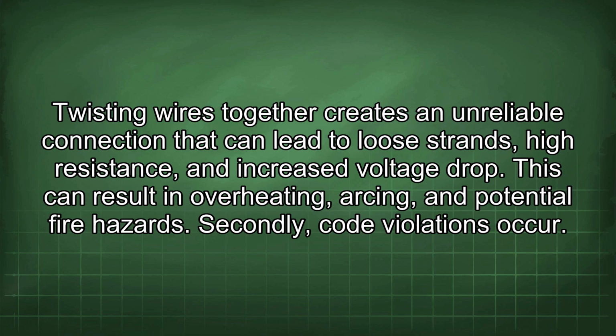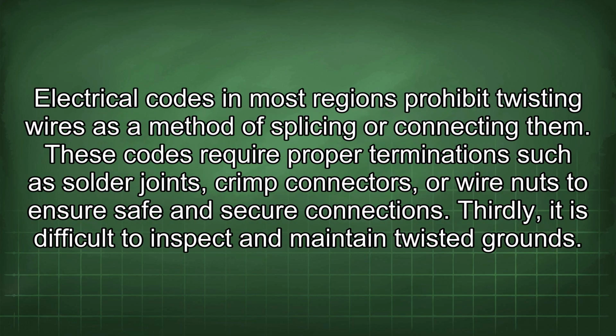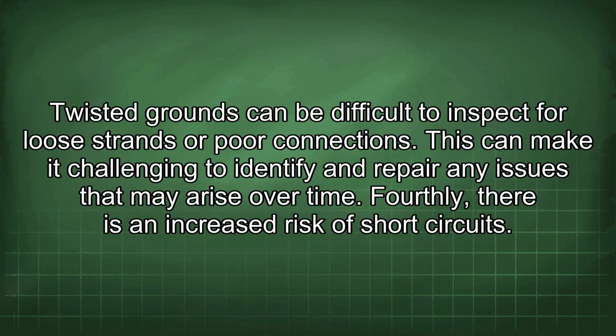Secondly, code violations occur. Electrical codes in most regions prohibit twisting wires as a method of splicing or connecting them. These codes require proper terminations such as solder joints, crimp connectors, or wire nuts to ensure safe and secure connections. Thirdly, it is difficult to inspect and maintain twisted grounds. Twisted grounds can be difficult to inspect for loose strands or poor connections. This can make it challenging to identify and repair any issues that may arise over time.